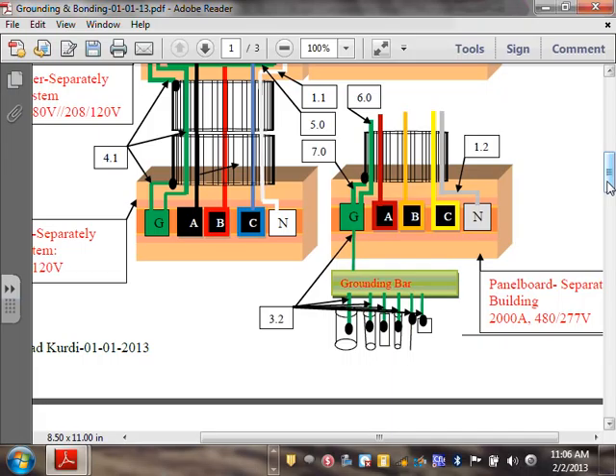Any comments, any questions? The other thing different in the second building is number 7 here. In the service, it's called the supply side bonding jumper because it's the supply side of the service. Here, it's the equipment bonding jumper, load side. Why? Because it's the load side of the service. Disconnect means the fuse, the circuit breaker. Any comment here about this?